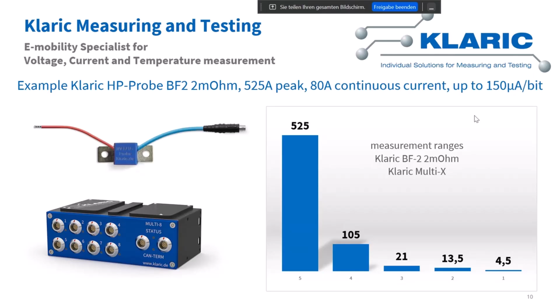And what does this mean in terms of accuracy? Klaric always measures 0.1% of the value plus minus 3 bit. The plus minus 3 bit comes from the measurement range, and the measurement range we change automatically. So I have a little example where we measure with this sensor up to 525 amperes peak current. When we measure 350 amps, we have an accuracy of around 400 milliamps, which is 0.07% of the value, quite good. But when automatically the current becomes smaller, like 80, 20, 10 amps, 4 amps, and even 1 amp, you can see the accuracy always becomes better, because it is 0.1% of the value, not of the range, and then plus minus 3 bit.